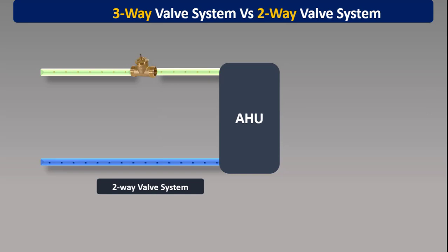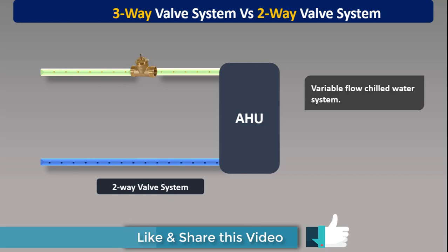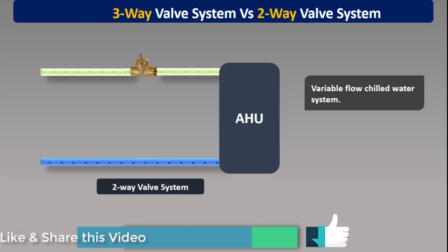In a two-way valve system, a two-port valve is used which has one inlet and one outlet. This system is a variable flow chilled water system. When a two-way valve is partially closed, this results in high pressure in the supply line. The BMS senses this increase in pressure and reduces the pump speed to achieve the desired pressure.